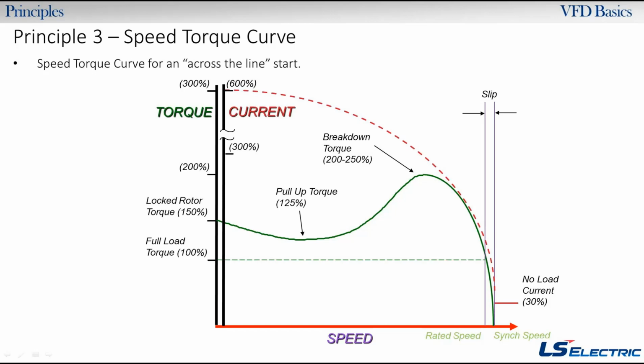So it's like a rubber band effect. Okay, so the slip is going to increase and increase and increase. And if you increase slip too much, you kind of overload the motor. You hit this breakdown torque, and then your torque just falls flat on its face. Okay, we don't talk too much about the motors in this webinar, but this is common for a NEMA design A or B motor. If you have a C or a D motor, your torque is going to go up a little bit more, especially with a design D motor. But yeah, most motors in the field are going to be like this. So eventually you get the breakdown torque where literally the motor can't produce any more torque.